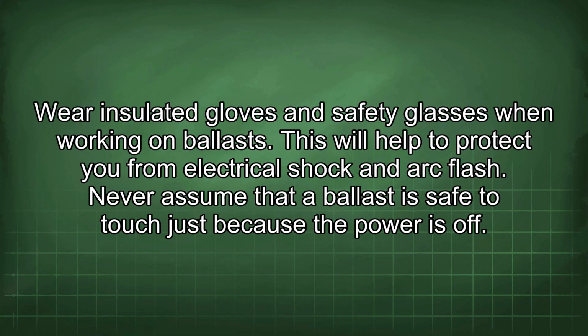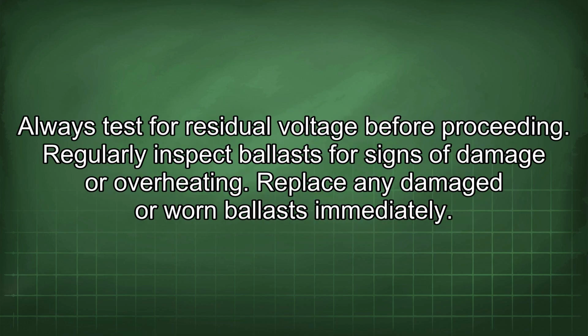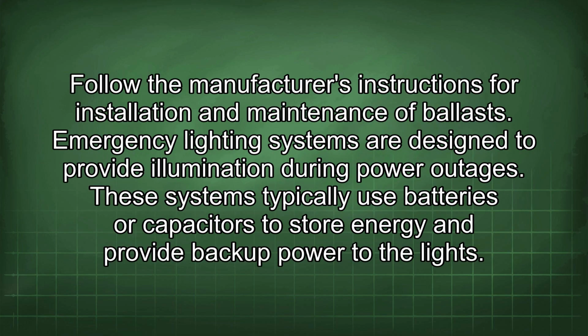Never assume that a ballast is safe to touch just because the power is off. Always test for residual voltage before proceeding. Regularly inspect ballasts for signs of damage or overheating. Replace any damaged or worn ballast immediately. Follow the manufacturer's instructions for installation and maintenance of ballasts.